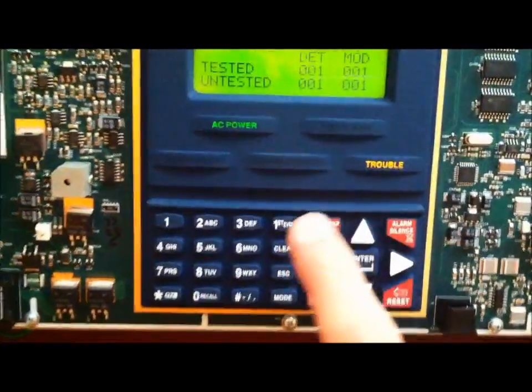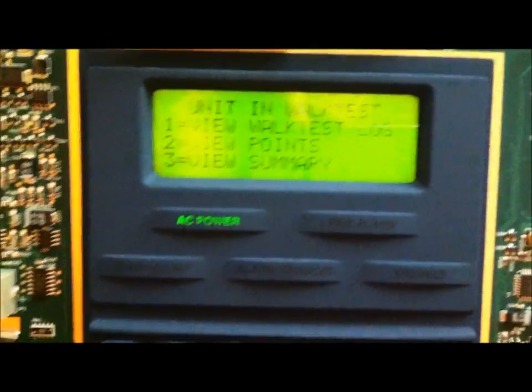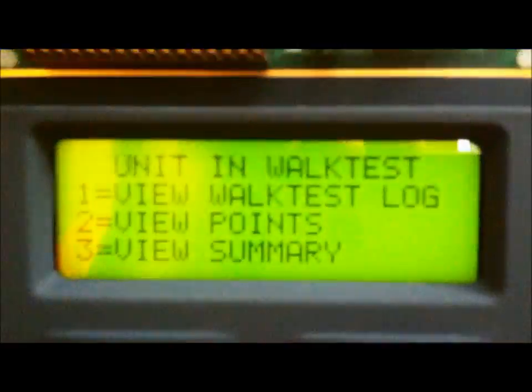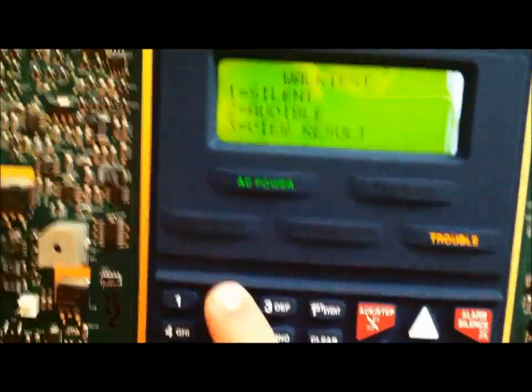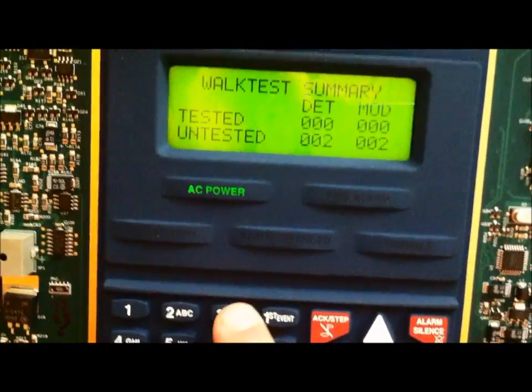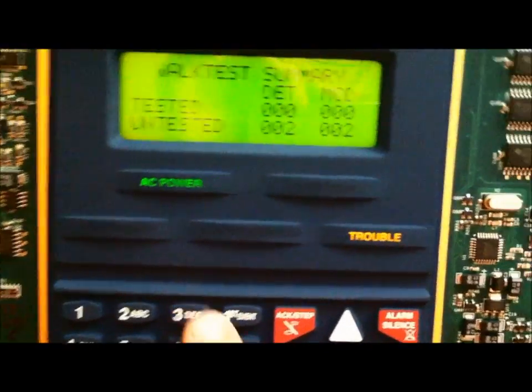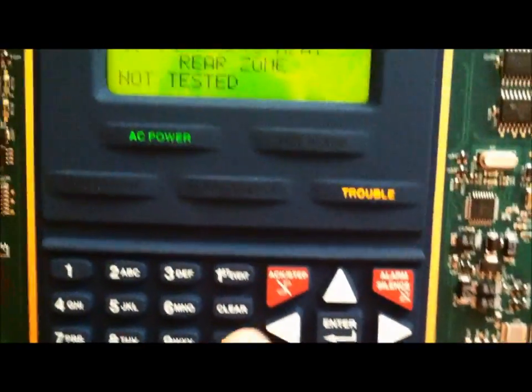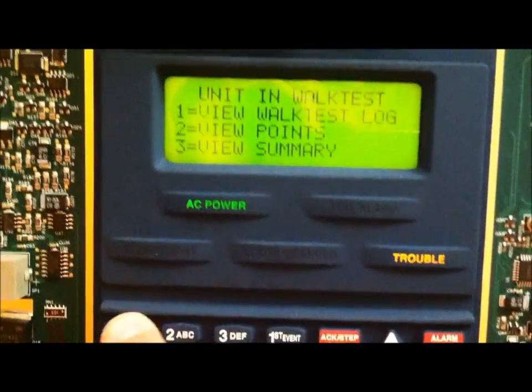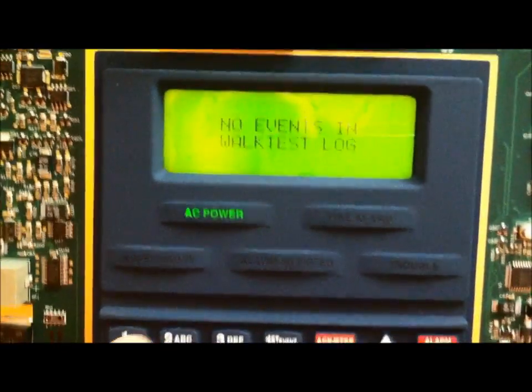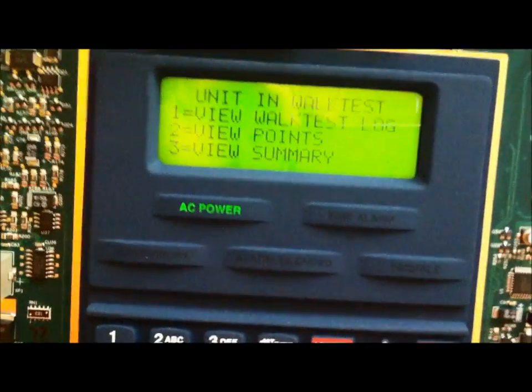Let me go ahead and exit out of this. Walk test mode. I'm going to make sure the pull station is reset. Okay, everything is good. See where it says Unit in Walk Test. I'm going to hit Escape. And now it just says Walk Test. I'm going to go back to that audible walk test I was in and view the summary. And everything is back to normal. Two untested. There are four untested points. And there's no events. So, everything resets.